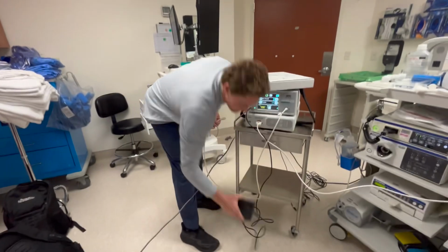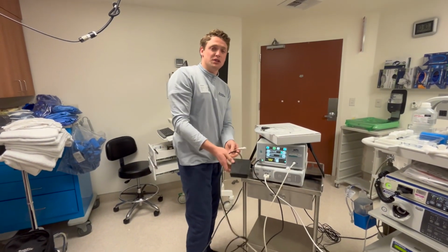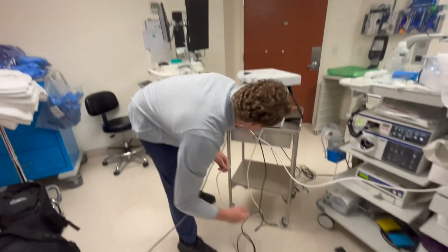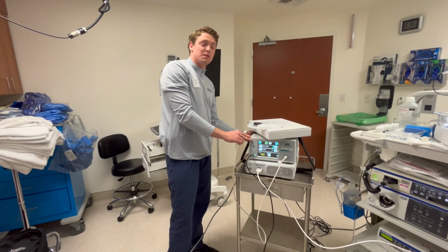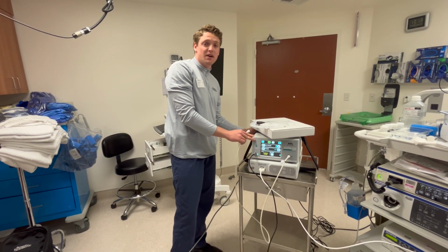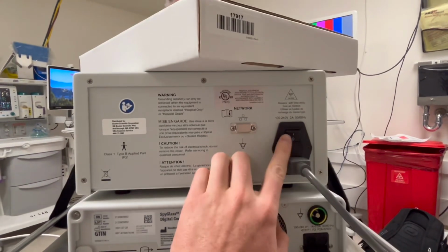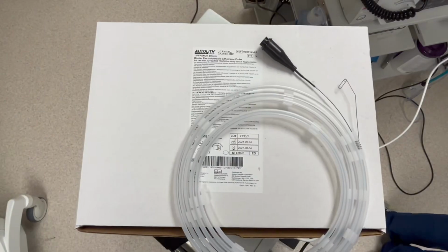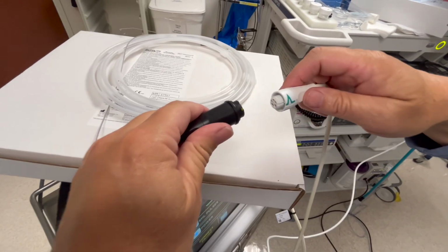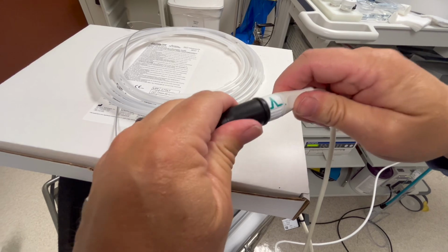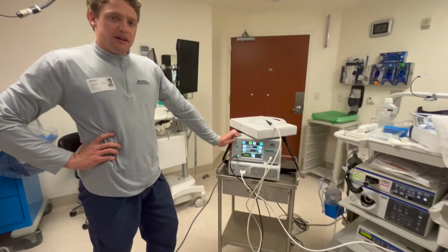A few steps for the EHL machine. 1, we're going to have our foot pedal. We're going to put this in the direction of where our physician will be standing. 2, we're going to want to make sure that we're plugged in and on. You're going to find that on the back. Connected. Make sure to have multiple EHL probes in the room. You'll connect the EHL probe to the white adapter, which connects to the Autolith machine.